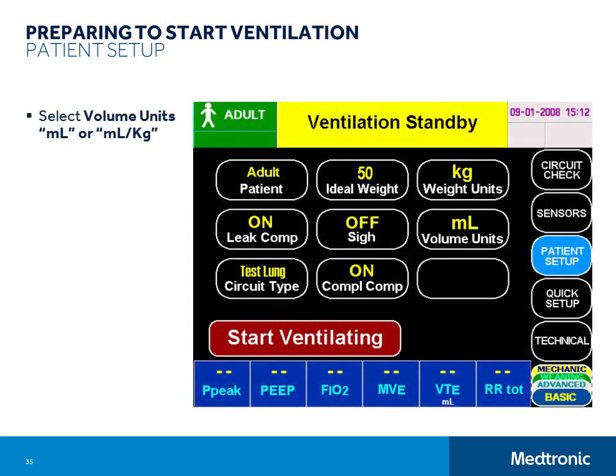Next, set the sigh function on or off. The sigh function gives a sigh breath every 100 mandatory volume control breaths. The sigh tidal volume is 1.5 times the set tidal volume.